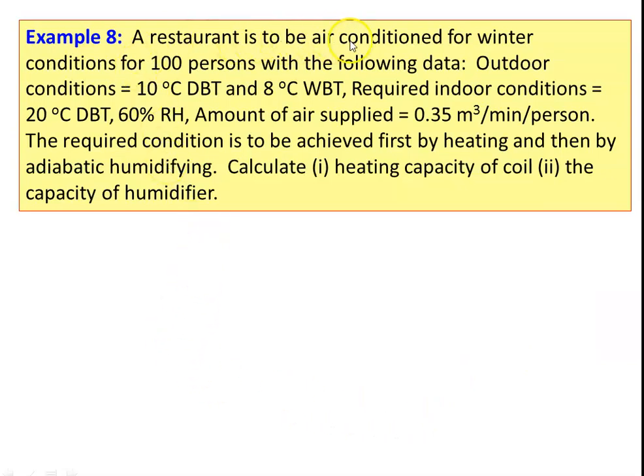Problem number 8: a restaurant to be air conditioned for winter conditions for 100 persons. Outdoor conditions: 10 degree Celsius dry bulb and 8 degree Celsius wet bulb temperature. Required indoor conditions: 20 degree Celsius dry bulb and 60 percent relative humidity. Amount of air supplied is 0.35 cubic meter per minute per person. The required conditions are achieved first by heating and then by adiabatic humidification.